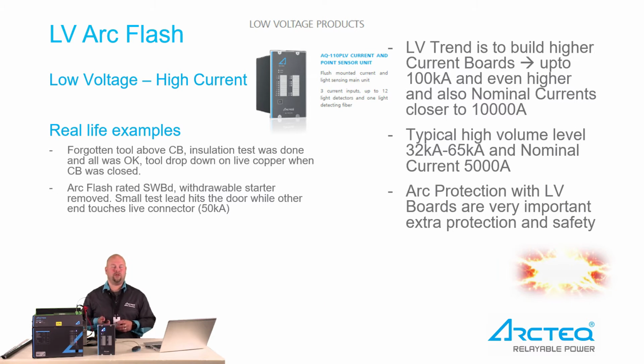Another example, another site a couple of years back, was a withdrawable starter, a very high quality switchboard with very high ratings. The transformer was very close to the low voltage board itself. When the electrician took the withdrawable starter out, an engineer went to do some testing with a test lead, a very thin wire. The purpose was to test 24 volt signals. Unfortunately, he ended up putting the test lead to the main voltage circuit, and the other end of the lead hit the door. And luckily he survived. There was arc flash protection installed, but the board was a little bit damaged because of the breaker delay.